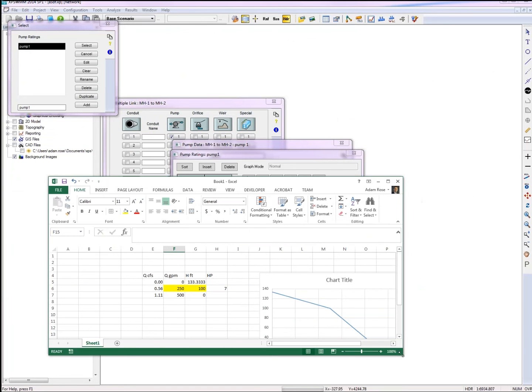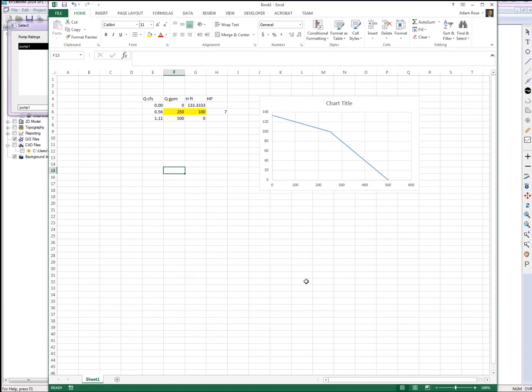Someone yell at me over here if you don't see Excel. I was talking to someone here, they thought this might be useful. Really simple way, and this is in the pressurized pipe world, of getting a three-point pump curve that covers all of your edge cases. The idea here is if I have a flow rate of, say, 250 gallons per minute and a head of 100 feet, that's my design point here, right? That's kind of what I want.